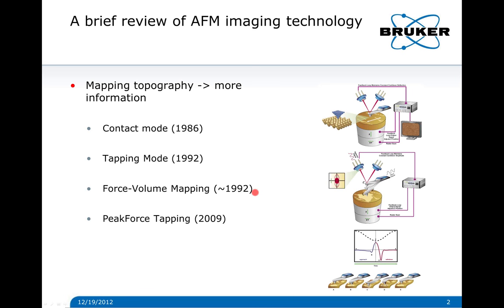About the same time, researchers were looking to expand beyond topographic imaging and used the AFM probe to learn more about the properties of their samples at the nanoscale. They already knew that they could use force curves to study the sample by ramping the Z position at one location and looking at the cantilever deflection. They realized they could collect these force curves at every pixel in the image, combining Z motion of the ramping and XY motion of the scanning to create a map of tip-sample forces while keeping lateral force to a minimum. Unfortunately, this technique is relatively slow and makes images with many pixels impractical.